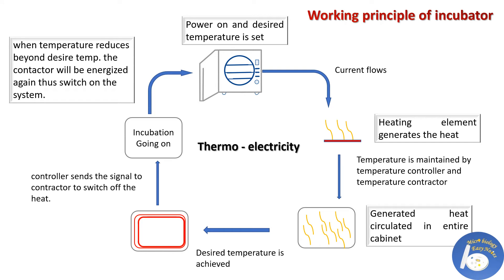The incubator works on a thermoelectricity system. Once the power is on and the desired temperature is set, current flows into the system, the heating element generates heat, and this temperature is maintained by a thermostat or temperature controller. The generated heat circulates throughout the entire cabinet. When the desired temperature is achieved, the temperature controller sends a signal to the contactor to switch off the heat. When the temperature drops below the desired level during incubation, the contactor energizes again, switches the system on, and current flows so the heating element generates heat again — this is how the temperature gradient is maintained.